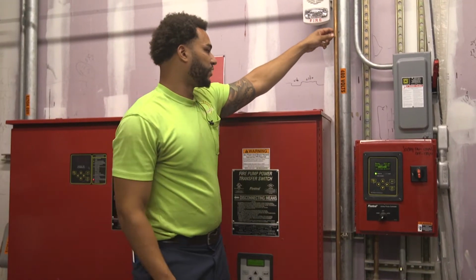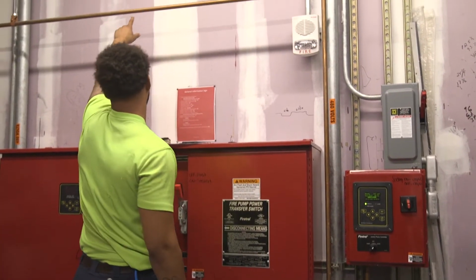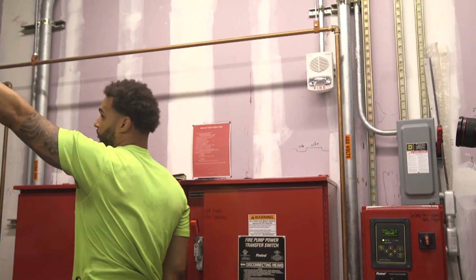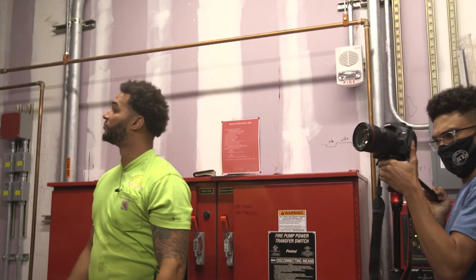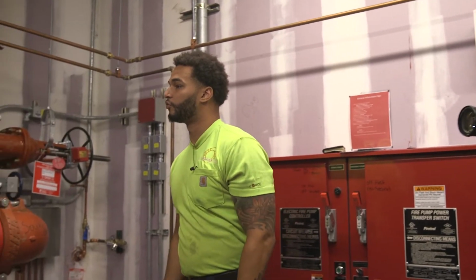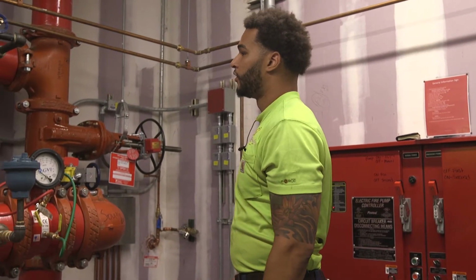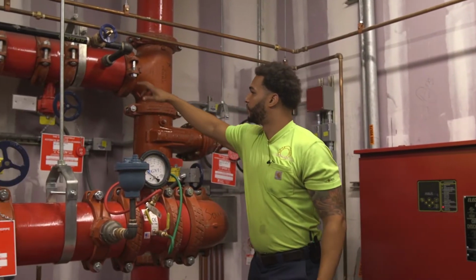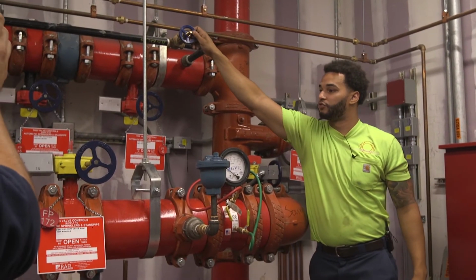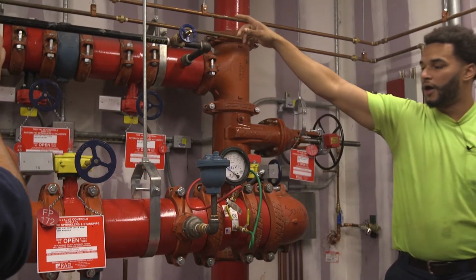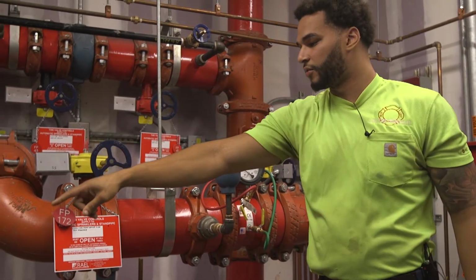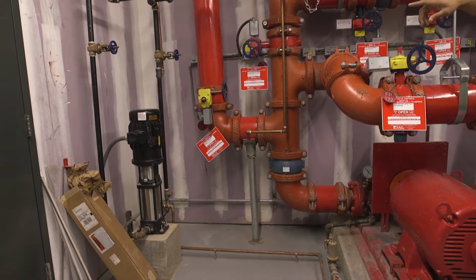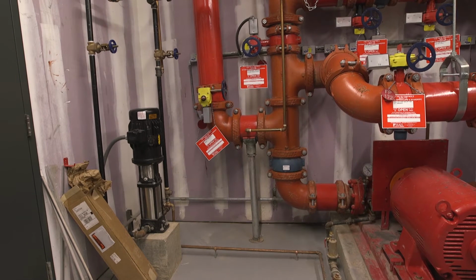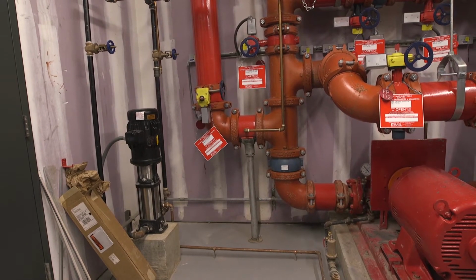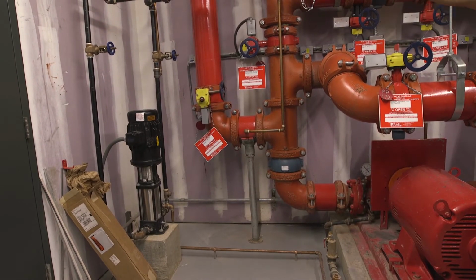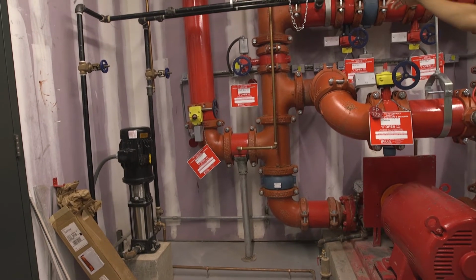So we have our sensing line that actually goes into our jockey pump, that taps into our jockey pump. The same sensing line is also made up of 2 unions. They're also pre-drilled with that 3/32 bit. So our jockey pump suction line has 2 isolation valves on it, and it travels right into the suction side of the jockey pump. So as we can see in our jockey pump piping, we have our suction line, which is piped into the suction side of the fire pump, and we have the discharge side, which is piped into the discharge side of the fire pump.